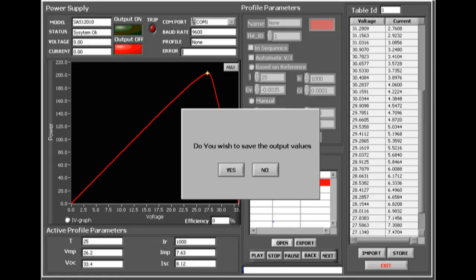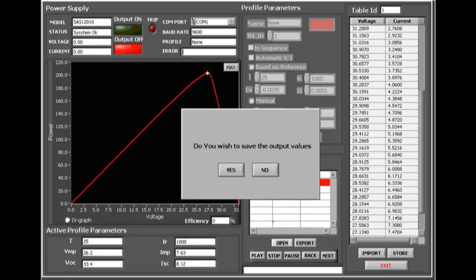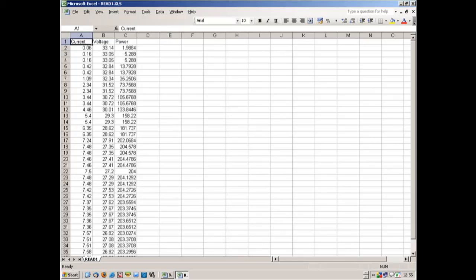Hitting the stop button makes the output turn off and prompts the user to save the recorded values for the test for future references with a date timestamp. The user has the flexibility to save it in any desired location. The report can be useful for R&D design characterization or QA verification and production quality control.